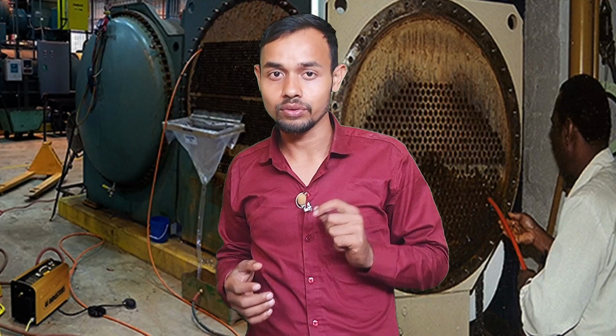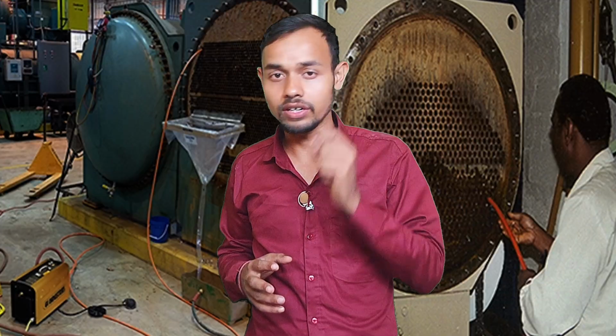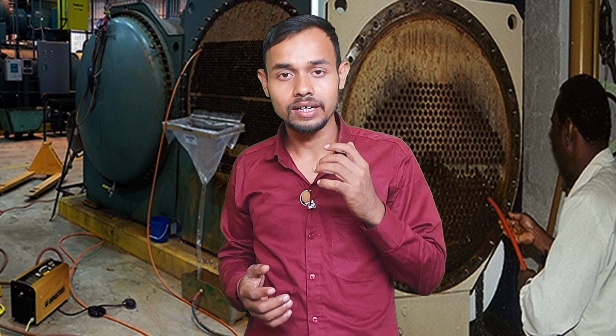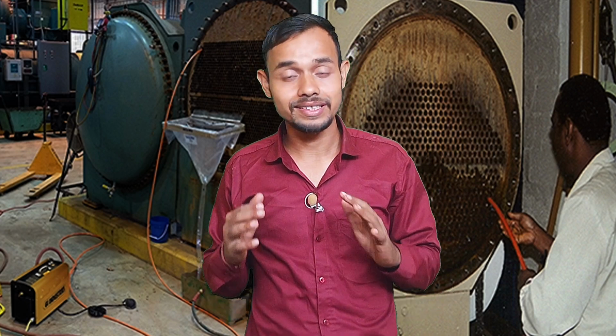Let's see in one line. Descaling is equal to tube cleaning plus restoring efficiency plus reviving the chiller. Okay, this is done on the condenser tube, and second the evaporator tube, and next in plate heat exchangers and shell and tube heat exchangers, and cooling tower piping also gets descaling. Okay, let's see the objectives of descaling.